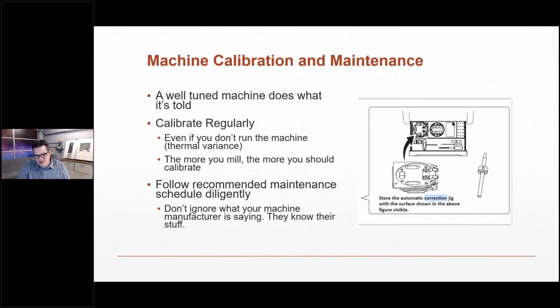Just take that documentation out and read it cover to cover, or the person in charge of running your mill should be reading it cover to cover and really understand it, and put a policy in place to calibrate based on what that documentation says. Generally, calibration is based on the interval of how many units you've run. So if you're running, for instance, 200 units a week, it might be good to do a calibration weekly, or something along those lines. Just take a look at the documentation, and that'll usually answer that question for you.